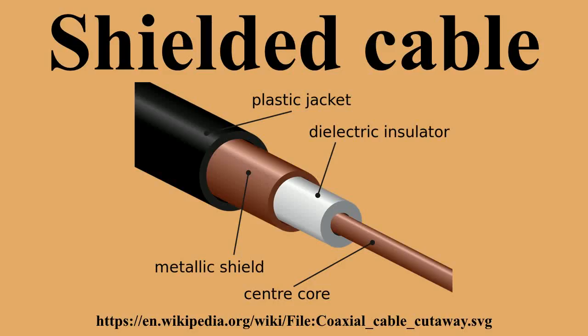Tests show that having a bare grounding conductor adjacent to the insulated wires will conduct the full current to earth more quickly. On high current circuits, the shields might be connected only at one end. On very long high-voltage circuits, the shield may be broken into several sections since a long shield run may rise to dangerous voltages during a circuit fault. There is a risk of shock hazard from having only one end of the shield grounded. The maximum recommended shield potential rise is 25 volts.